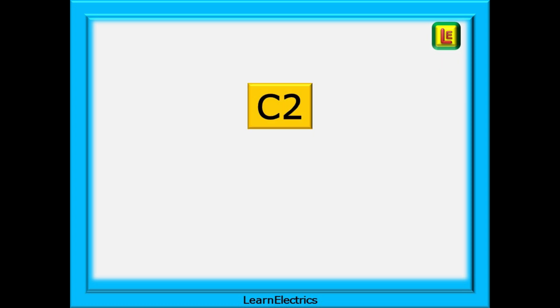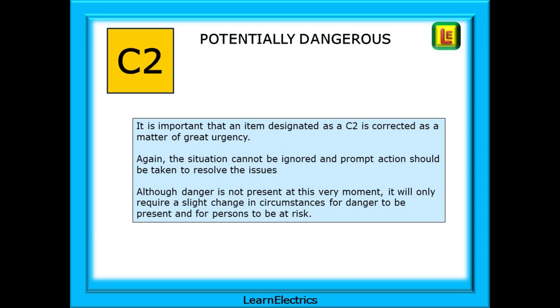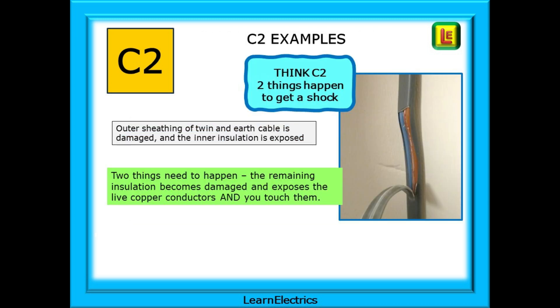Moving on to C2 observation codes. C2 codes are used for something that has the potential to be dangerous. It's important that an item designated as C2 is corrected as a matter of urgency. The situation cannot be ignored and prompt action should be taken to resolve the issues. Although danger is not present at this very moment, it will only require a slight change in circumstances for danger to be present. For example, the outer sheathing of a twin and earth cable is damaged and the inner insulation is exposed — two things need to happen: the remaining insulation becomes damaged and exposes the live copper conductors, and then you touch them. Think C2: two things happen to get an electric shock.